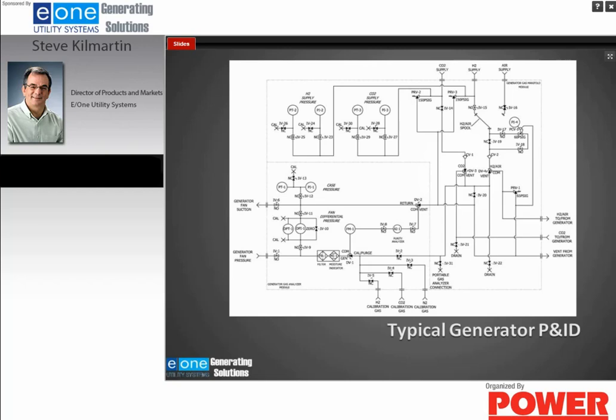Now, during the purging process, which I'm going to discuss in a little more detail later, the three-way valve that you see below the flow meter, labeled Cal Purge, we would put in the Cal Purge position, and then the analyzer would either be getting gas from the calibration gases, which would be the H2 calibration gas, CO2 calibration gas, or nitrogen calibration gas. By the way, we use nitrogen as a calibration gas instead of air just because it's not explosive when mixed with hydrogen. Or you can see that there's another line that goes up into the vent. This is very important because this is where we will take our purge sample when we're purging the generator, and we'll discuss that later.